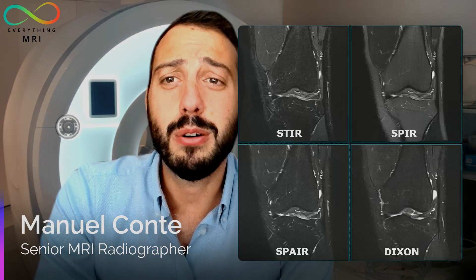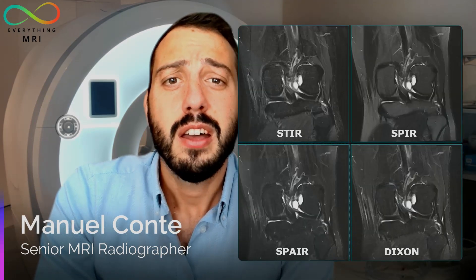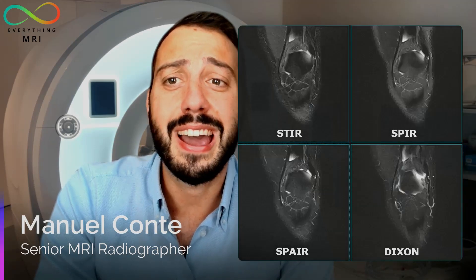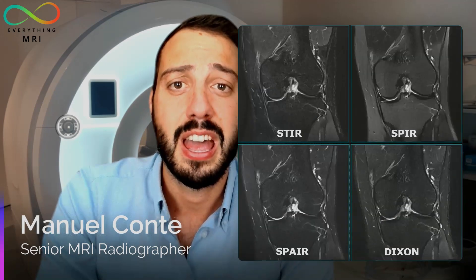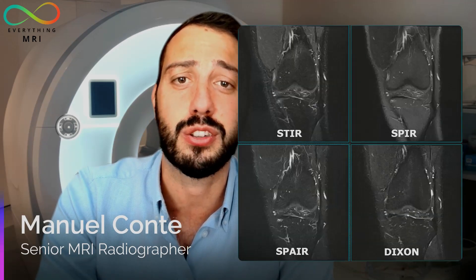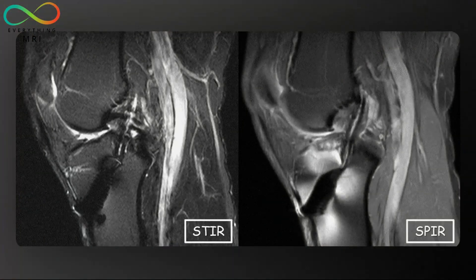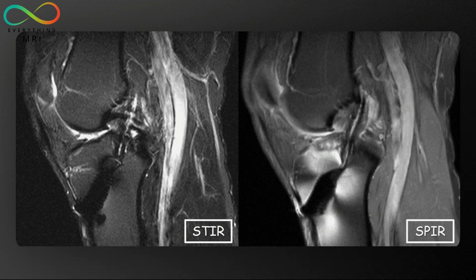An additional consideration is about the type of fat saturation to be used. Some sequences are more recommended than others because they are not particularly affected by magnetic field inhomogeneity. Make sure to check the video on different fat saturation techniques on the Everything MRI YouTube channel. In general, STIR sequences can be considered the sequences of choice for fat saturation when imaging patients with metal implants, as they are much more resistant to B0 inhomogeneity compared to sequences with spectral suppression of the fat signal, like SPIR for example. We can clearly see that signal loss and signal pileup are significantly less pronounced when STIR is acquired.